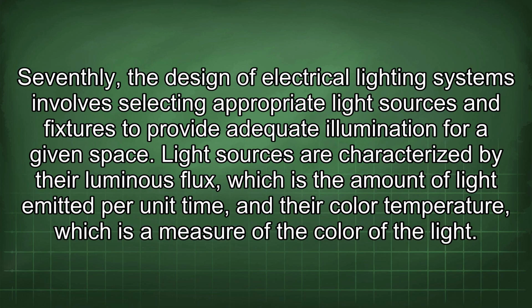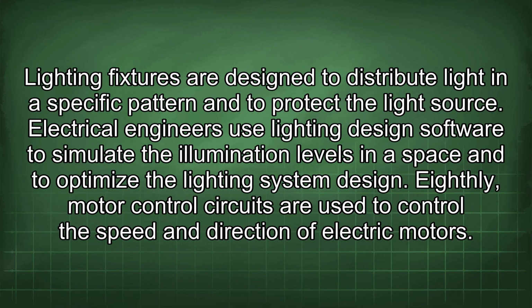Seventhly, the design of electrical lighting systems involves selecting appropriate light sources and fixtures to provide adequate illumination for a given space. Light sources are characterized by their luminous flux, which is the amount of light emitted per unit time, and their color temperature, which is a measure of the color of the light. Lighting fixtures are designed to distribute light in a specific pattern and to protect the light source. Electrical engineers use lighting design software to simulate the illumination levels in a space and to optimize the lighting system design.